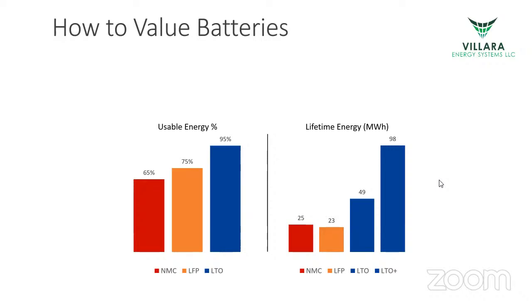When a home battery is installed, the installer sets a lower limit and an upper limit on the state of charge, because batteries wear out too quickly if you let the charge get too low or too high. LFP batteries, for example, are typically installed with a lower limit of about 15% and an upper limit of 85 to 90%. But 15% to 90% means only 75% of the battery is actually usable on a daily basis.